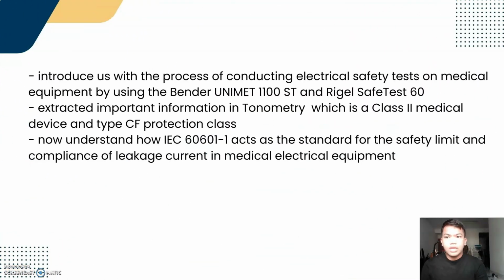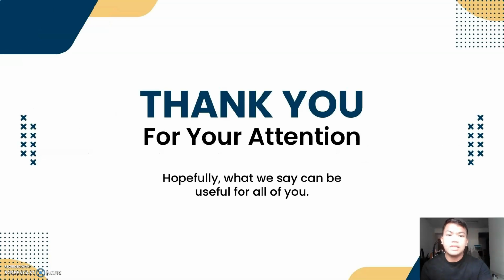For the conclusion, in this assignment, we introduced ourselves to the process of conducting electrical safety tests on medical equipment by using the Bender and Rigel 60. And we successfully extracted important information on the tonometer, which is a class 2 medical device with type CF protection class. And we also now understand how IEC 60601 acts as the standard for the safety limit and compliance of leakage current in medical devices. That's all from us. Thank you.